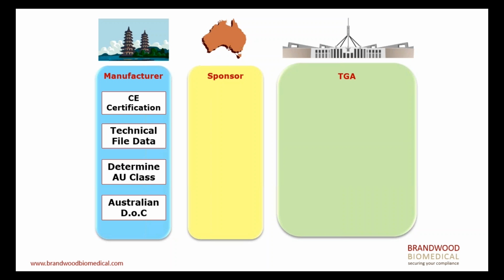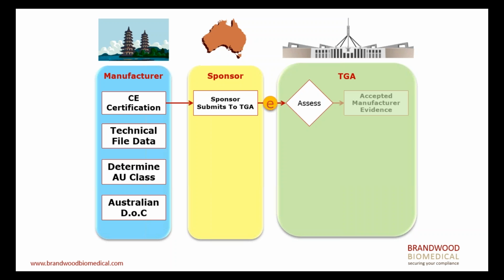Basically, then you want to register your product. The manufacturer first submits the CE certification to the sponsor, and the sponsor would then submit this to TGA. Now, the e-portal is an online electronic portal. It's the Business Services portal. The sponsor submits that to TGA, and that gets assessed. So, for example, if it's a Class 2B and the manufacturer gives them an Annex 2.3 certificate for full quality assurance, TGA will assess that, and if that's accepted, they'll accept the manufacturer's evidence. So that will be considered as the manufacturer's evidence.